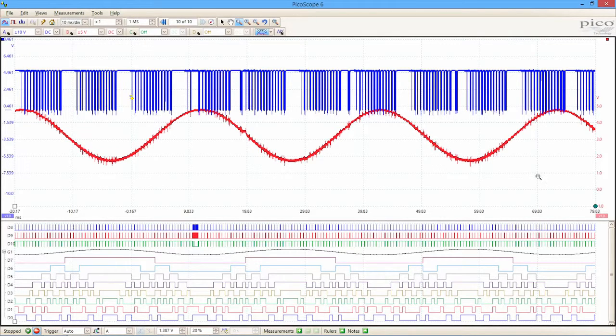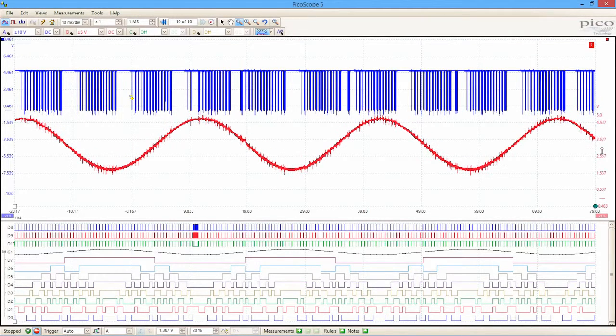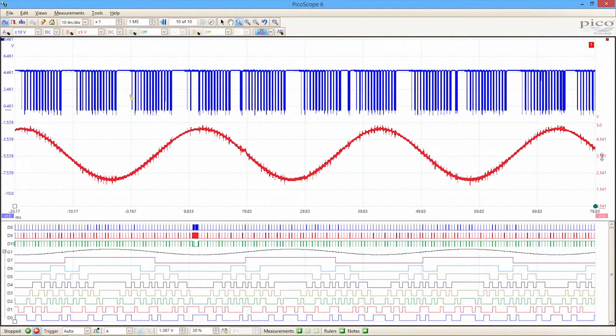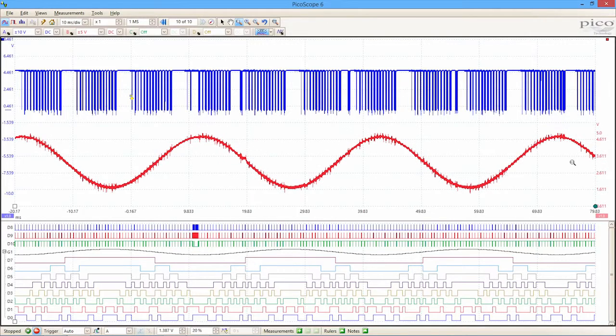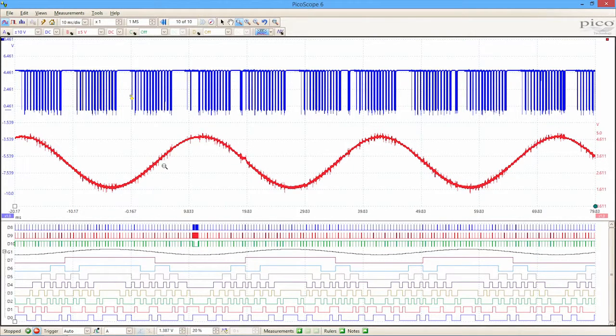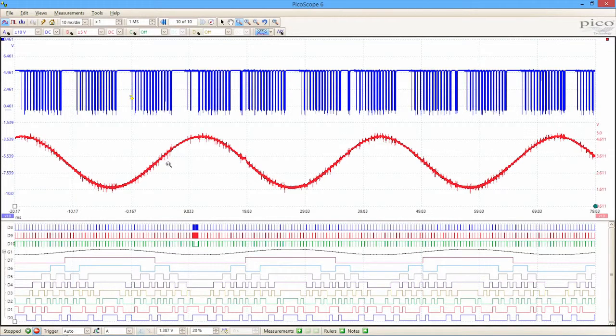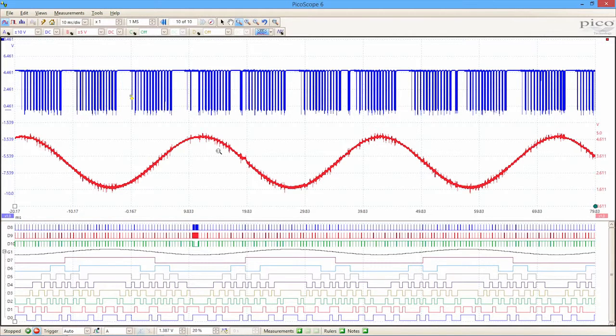And then on the top display, we're looking at the real analog data, which is the output from the digital to analog converter, complete with any noise and imperfections, missing bits and so on, that might be the cause of a problem that we would need to investigate.